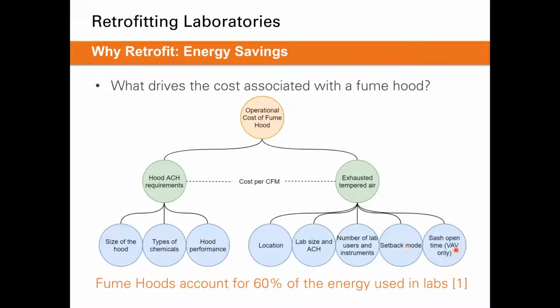And finally, this last bubble here, the sash open time, the percentage of time that the sash is open. And I put this note here, VAV only. So it would only be a variable with VAV hoods, because CV hoods would just constantly be exhausting the air no matter what. But sash management does play a huge role in how effective your VAV solutions are.